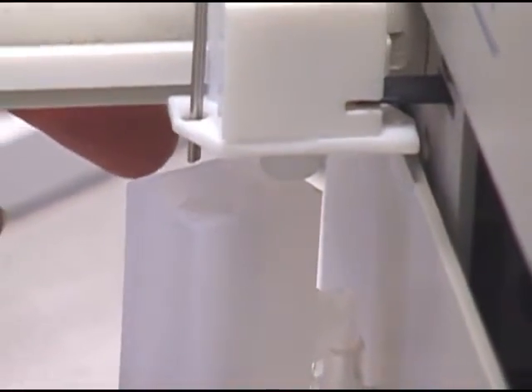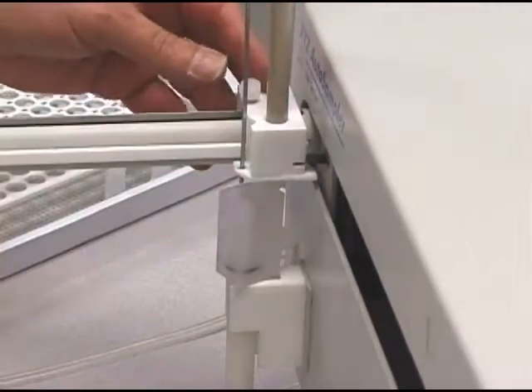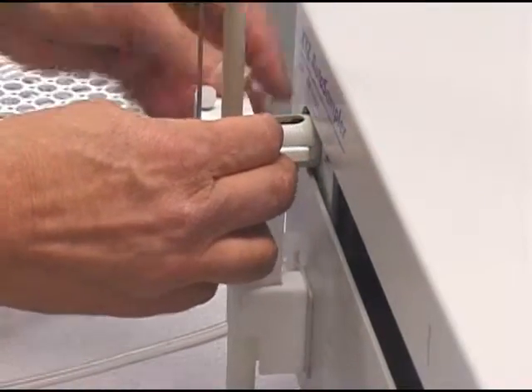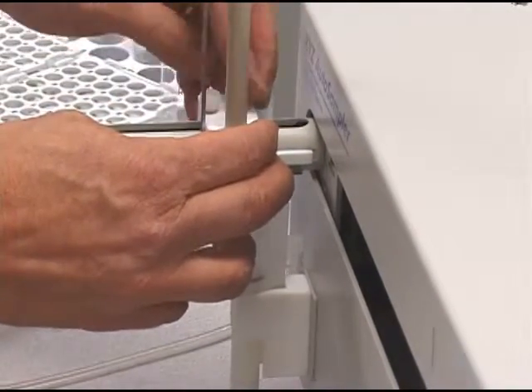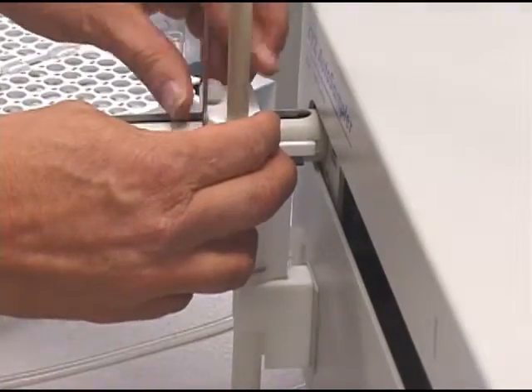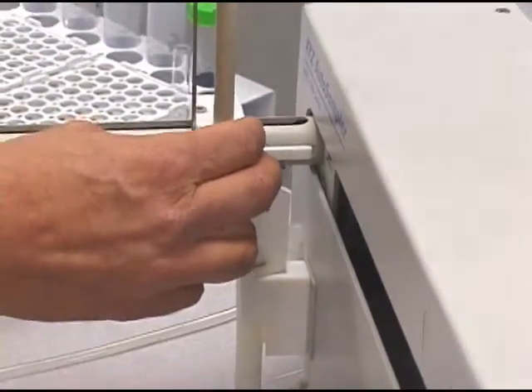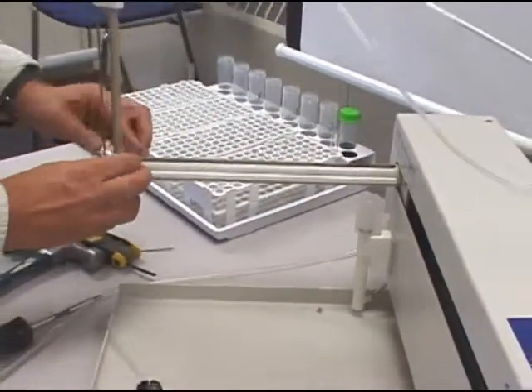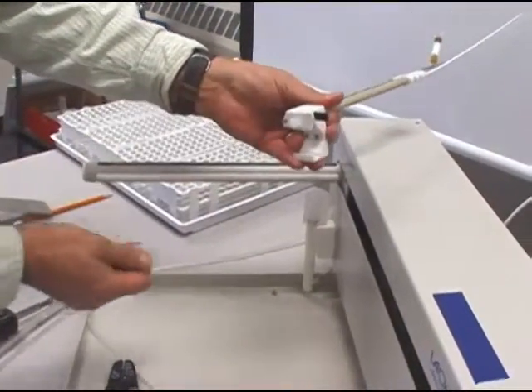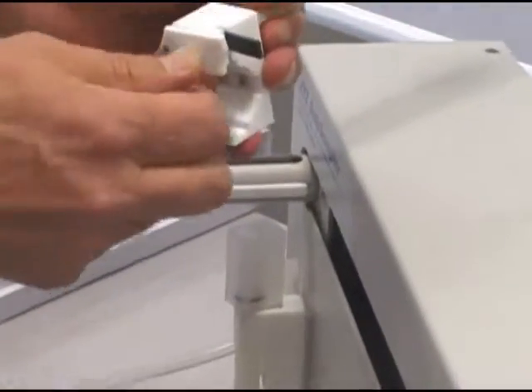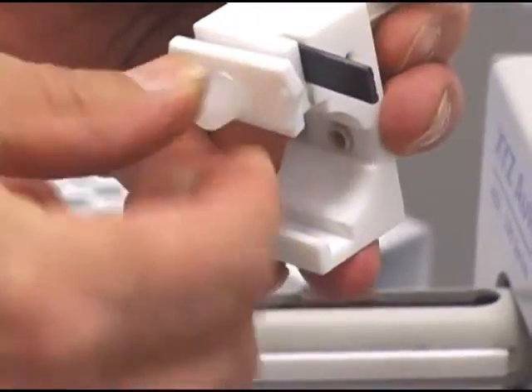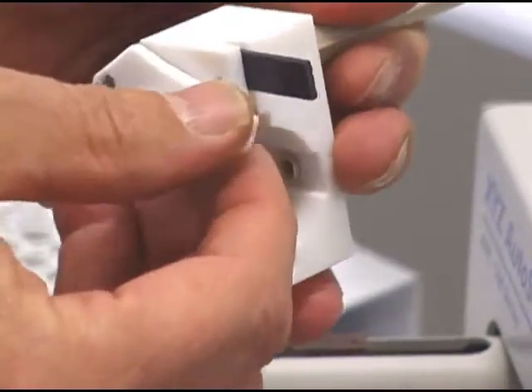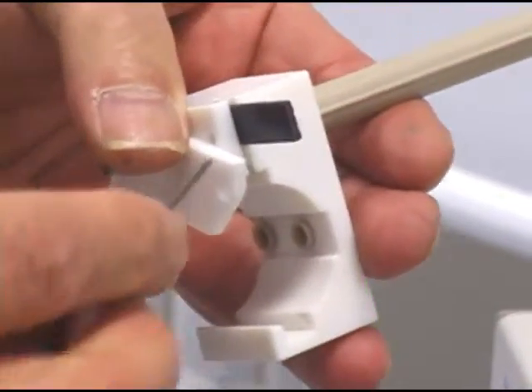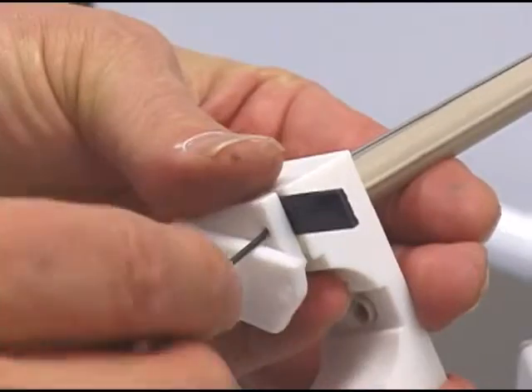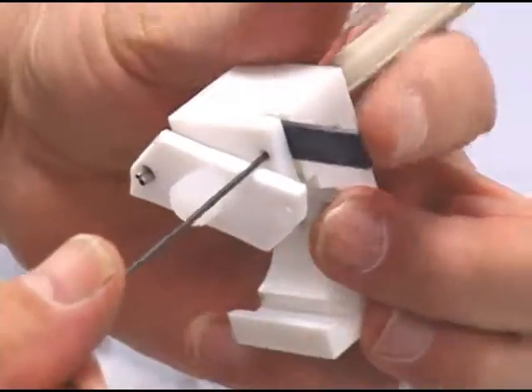And to extend that flag, turn the autosampler off. You'll need to remove the assembly, so pull it back a little bit. Remove these screws. Take your assembly off. And you'll remove this bottom plate, or loosen it actually, so that you have access here to this 50 thousandths Allen head screw, which holds this flag into position.